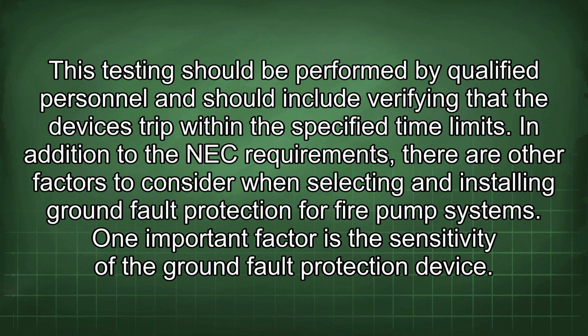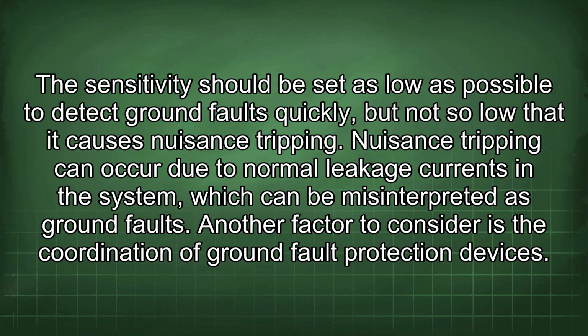In addition to the NEC requirements, there are other factors to consider when selecting and installing ground fault protection for fire pump systems. One important factor is the sensitivity of the ground fault protection device. The sensitivity should be set as low as possible to detect ground faults quickly, but not so low that it causes nuisance tripping. Nuisance tripping can occur due to normal leakage currents in the system, which can be misinterpreted as ground faults.